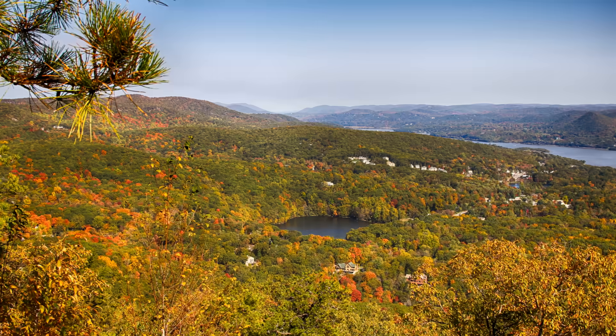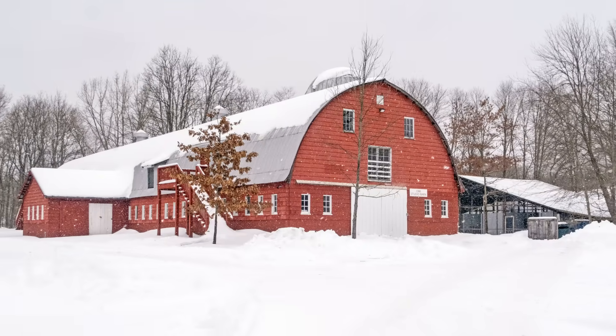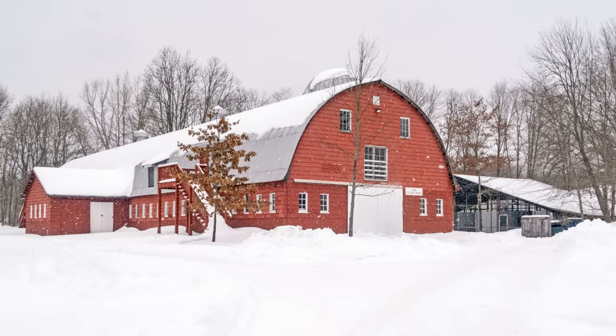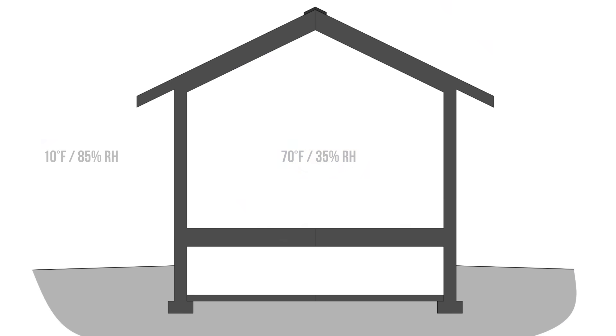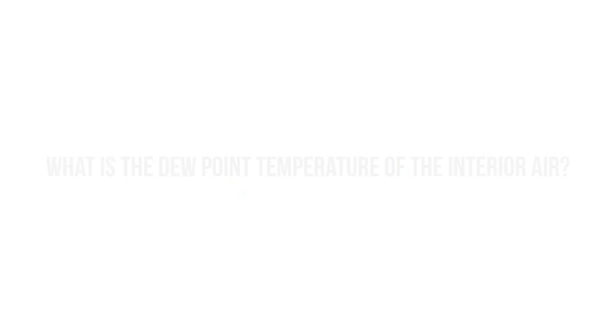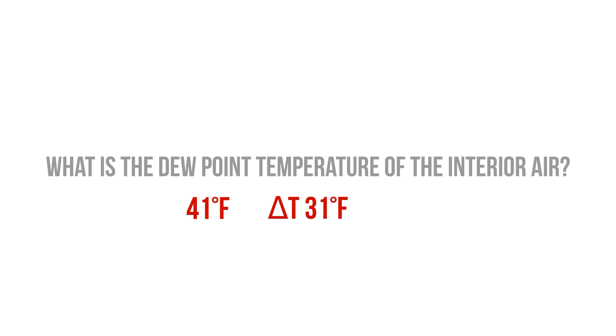Let's say that you live in upstate New York, where during the winter months, nighttime lows can easily be below 10 degrees Fahrenheit, and let's say that you're operating at 70 degrees Fahrenheit at 35% relative humidity, which is fairly common. What is the dew point temperature of that interior conditioned air? It's about 41 degrees — nearly 30 degrees higher than the temperature outside.